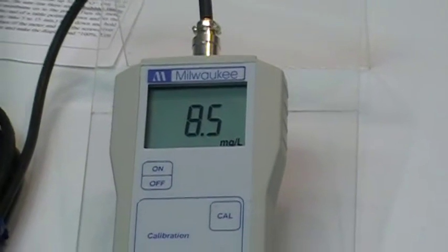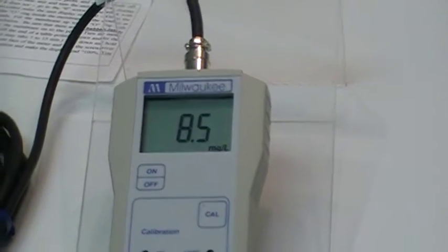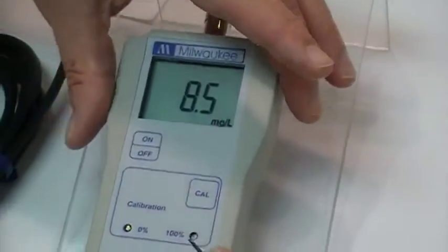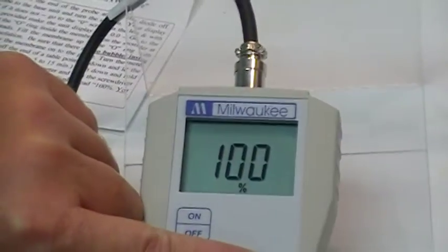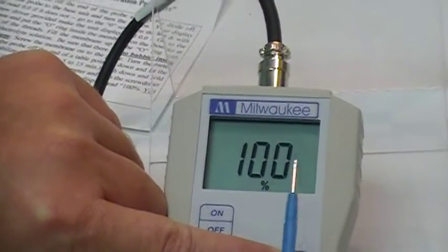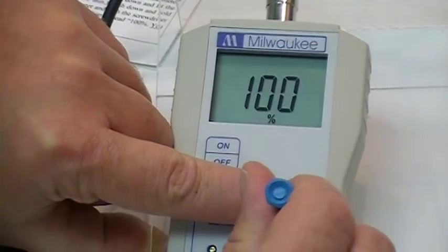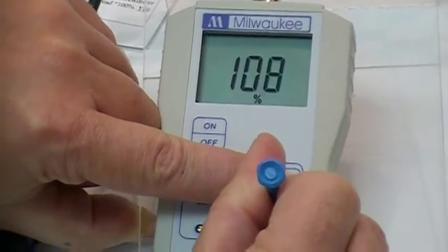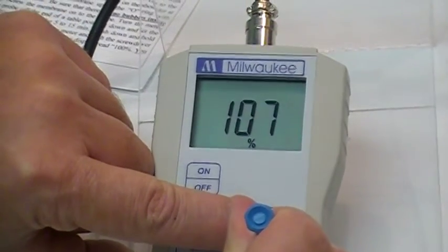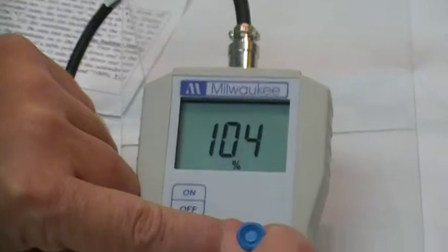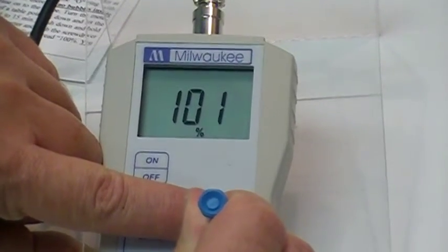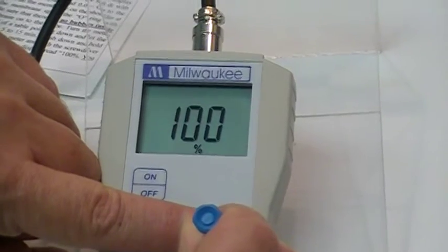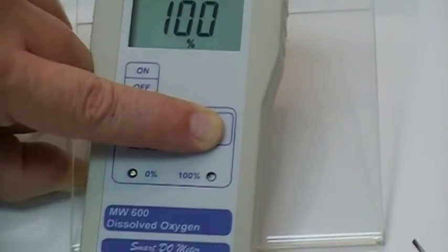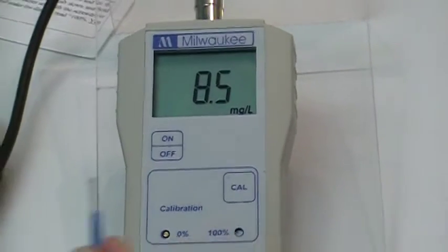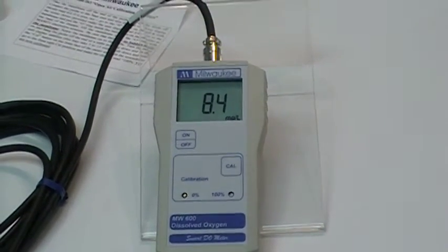For the sake of shortening this demo, we're going to go ahead and do the 100% cal position. So as you see, it's sitting at 8.5 right now. We're going to hit the cal button, and as it turns out, it's already sitting at 100. But if it was not sitting at 100, what you would do is take the screwdriver and dial it. It is a little bit touchy, so it doesn't take much movement. Hold down the cal button until you come to 100. Release the cal button.